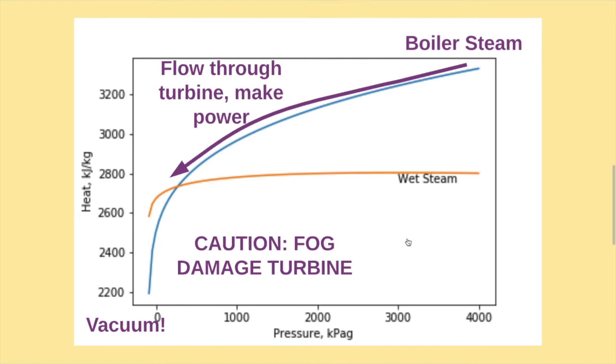The pressure keeps dropping, and we create a vacuum. We also create fog, and this is a problem. I forgot to tell you that the steam is traveling at about 150 meters per second, or 540 kilometers per hour. Turbine blades are damaged very quickly when hit with tiny drops of water at this speed. There is a very practical limit to how much heat we can convert to work.